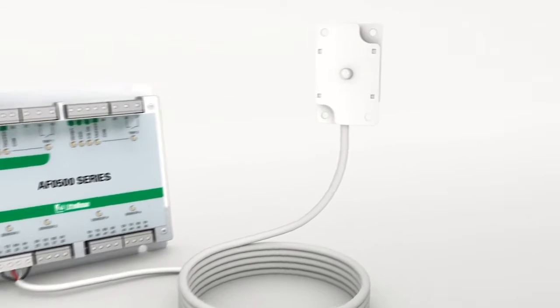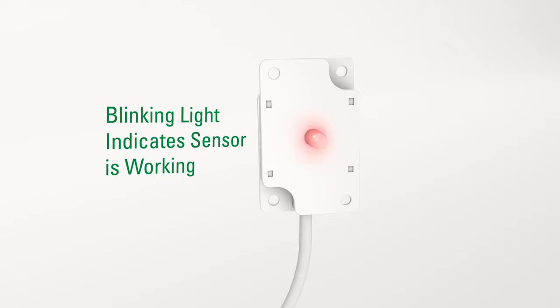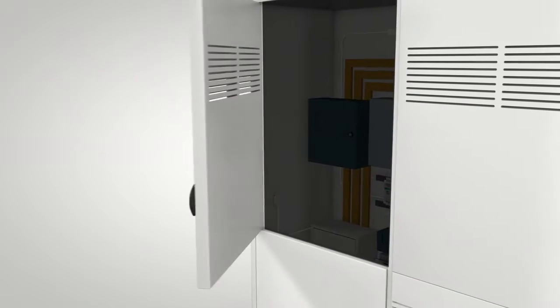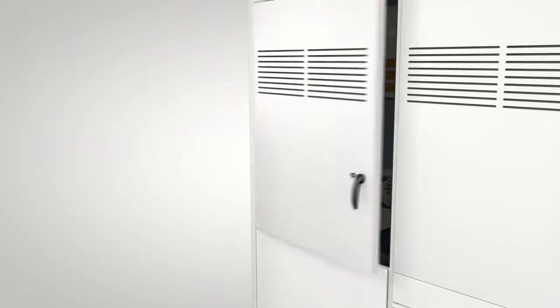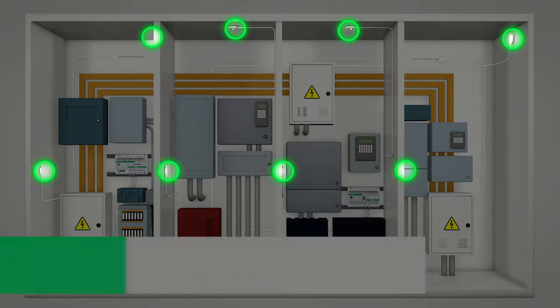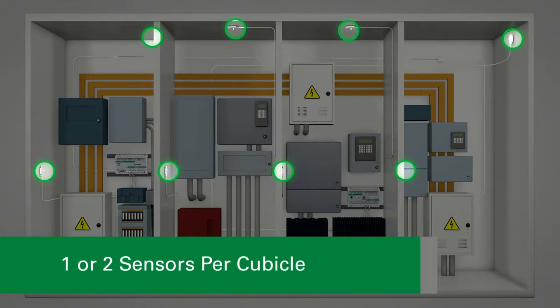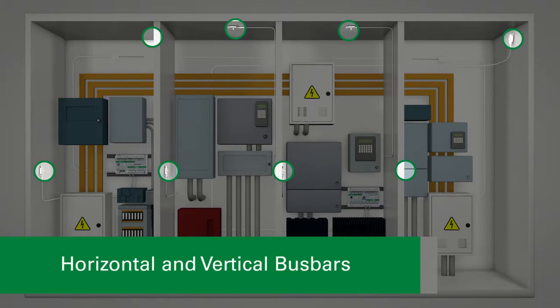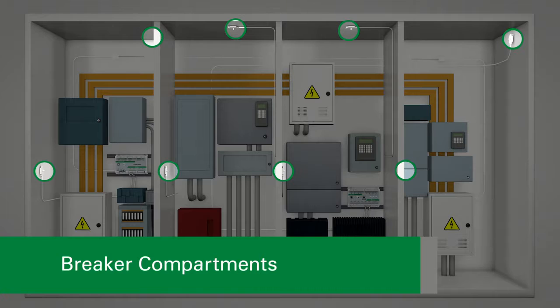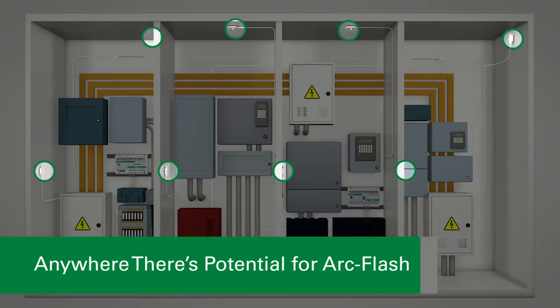The sensor's red flashing light tells you the sensor is installed correctly and working. This visual indication serves as a warning to workers. If they open a cabinet and there's no light, they know to close it immediately. Littelfuse recommends mounting 1 or 2 sensors per cubicle to cover all horizontal and vertical bus bars, breaker compartments, and anywhere there's potential for an arc flash.